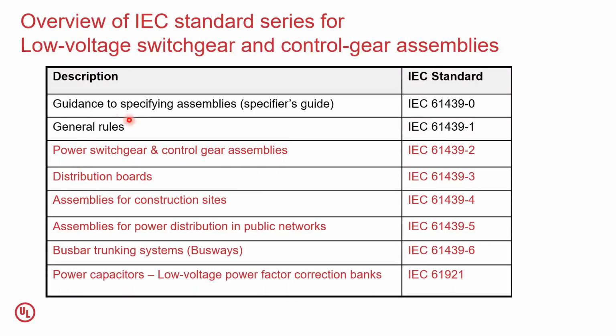The first two standards are not necessarily product standards. The first standard is also called a guide. It is mainly for the people who are specifying assemblies, used by the consultants, and could be used by regulators. It could also be used by testing houses and manufacturers. So primarily it sets out what you need to specify. For example, if you are specifying a busway, would you like the busway accessories also to be tested? Because many times what normally happens is only the straight length and the joint gets tested. Unless you specify, I also need the elbows tested, I also need the flanges tested, more likely the testing may not happen on those. So that is one example.